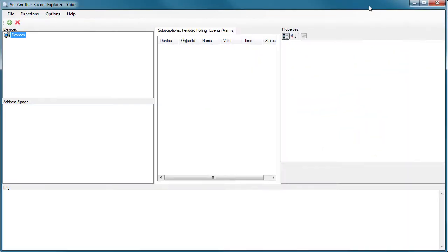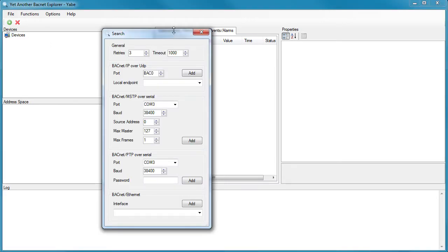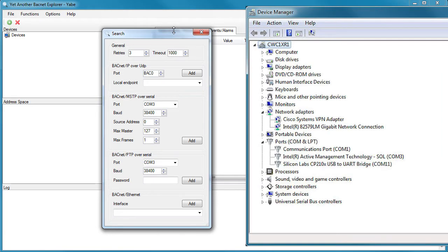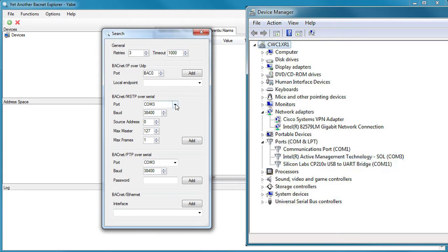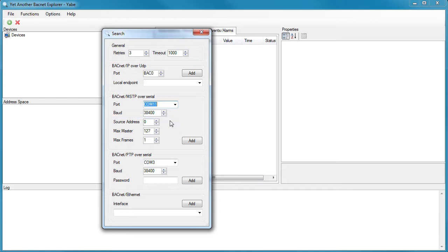When you launch this app, you get a blank screen. First we have to tell it which transport protocol we are going to use, so right-click and add a device. The GS4 drive uses the MSTP transport protocol. I see in my Windows Device Manager that my USB to 485 converter is on COM port 11, so that goes here. The baud rate is exactly what we want, and we'll have it start at address 0 and search for devices through address 127. Remember, we just set ours to address 99, ID 37.